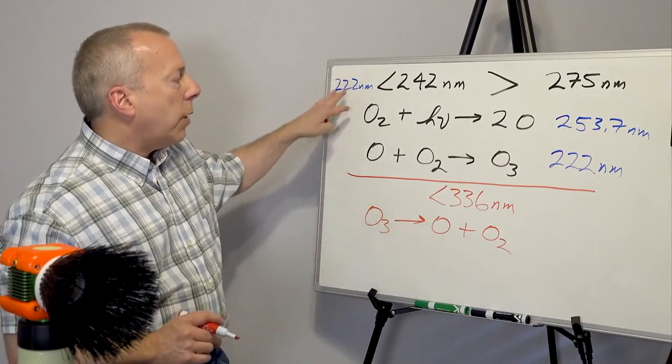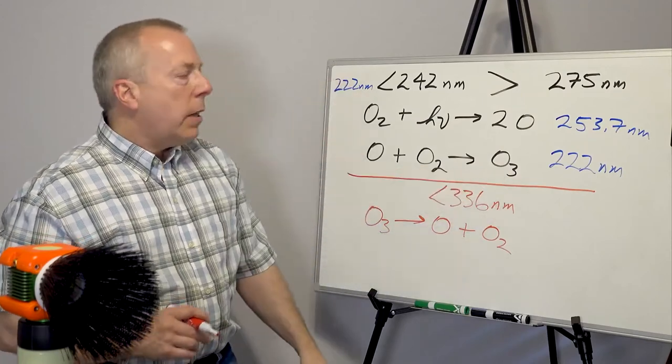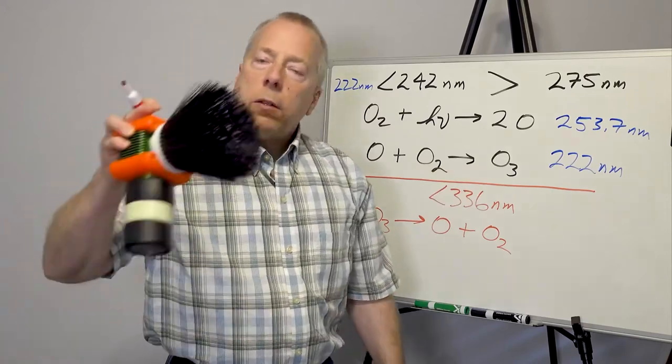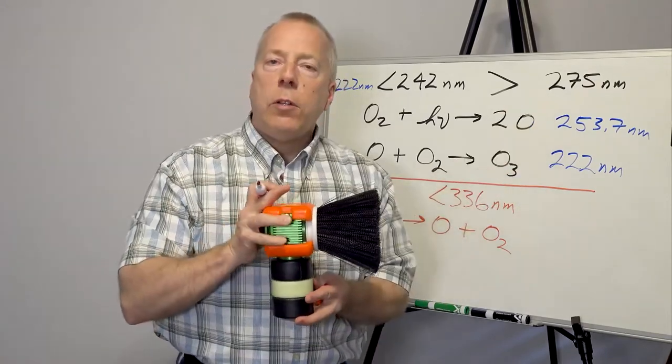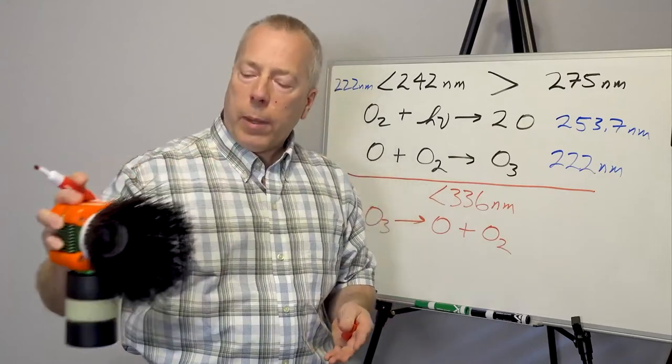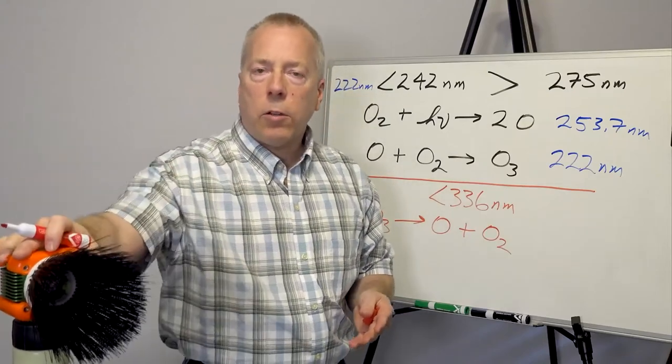But the 222 excimer actually generates ozone. Our UVC body light does not. So it's sitting at 275 nanometers, and there's no ozone generated by operation of this particular light.